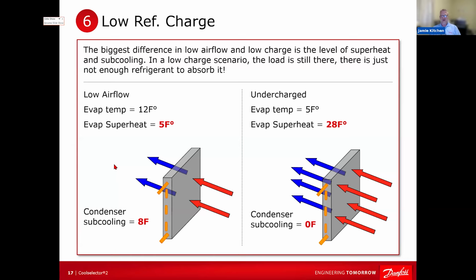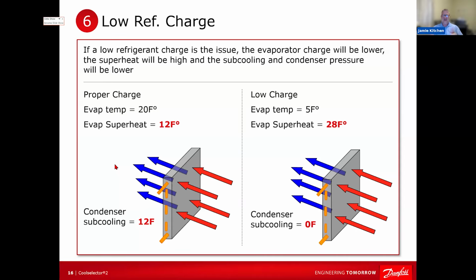Your condenser subcooling, right? Whoops. What happened here? There we go. 12 degrees. Maybe it's a bit high, right? Maybe it's supposed to be 10, 8. But the point is you have a solid column of liquid leaving your condenser or close to it. So if you've got good subcooling, you ain't got a low refrigerant charge. That is not an issue. You have enough refrigerant in the system, right?